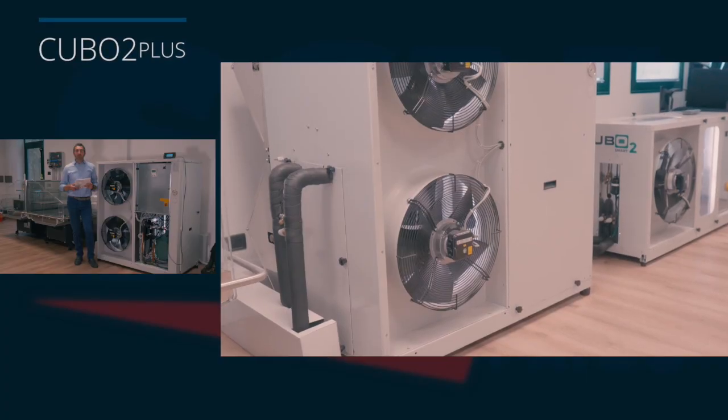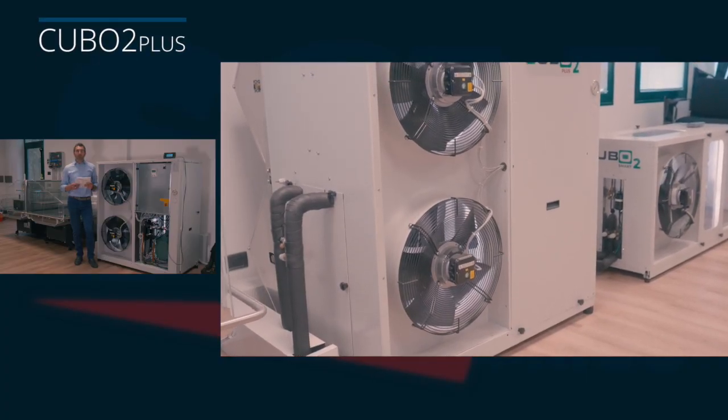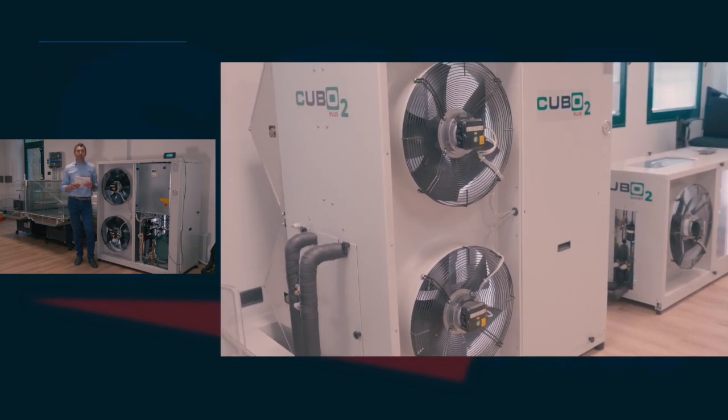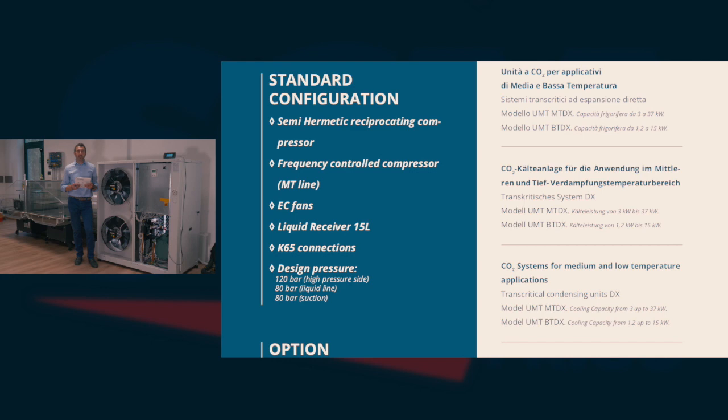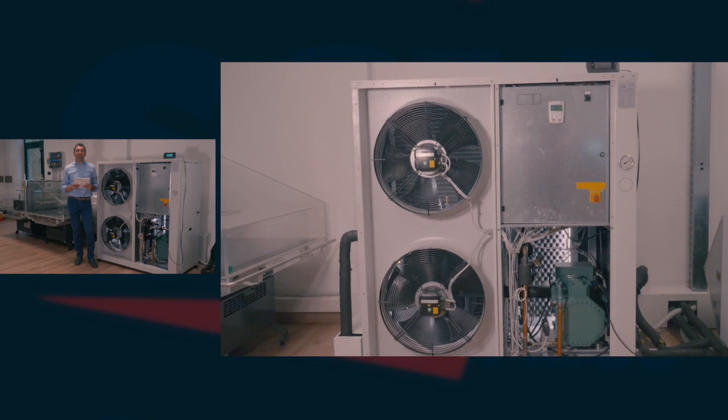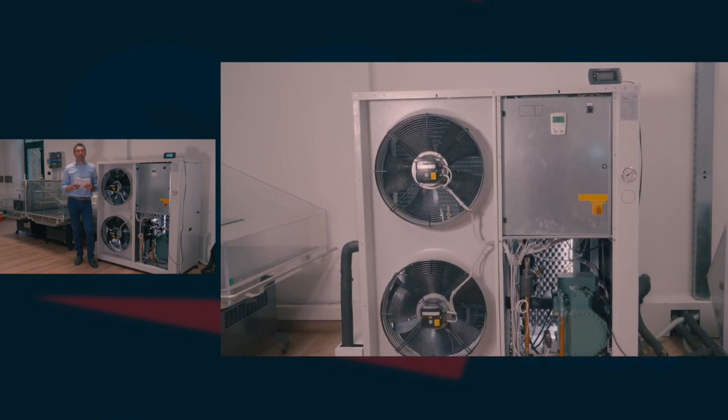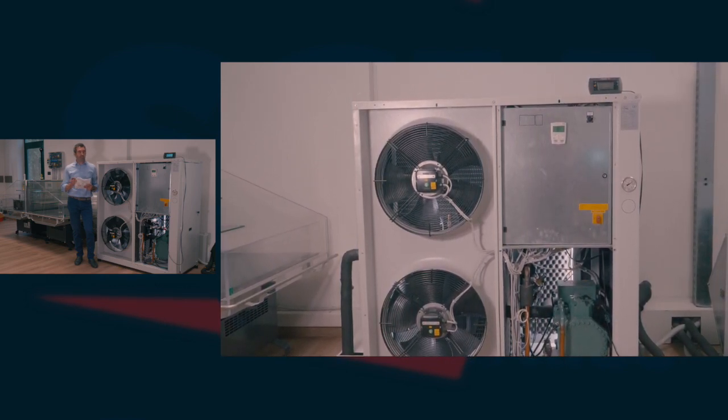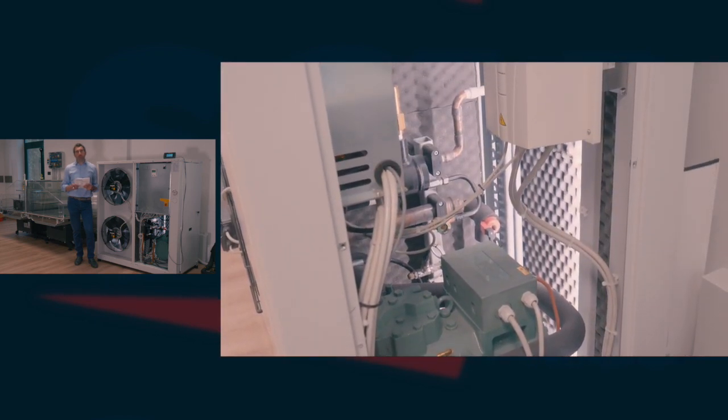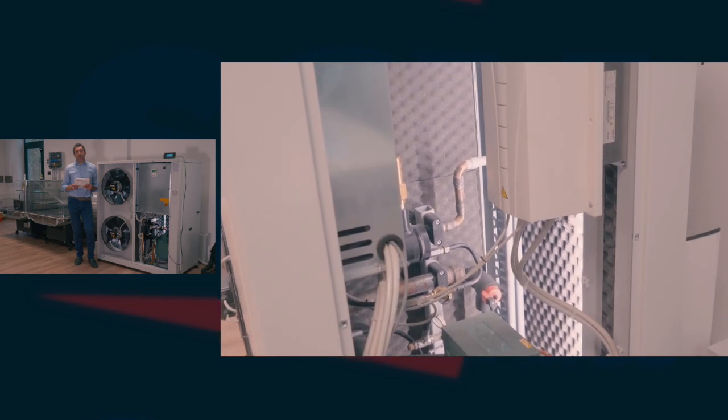This is a medium temperature condensing unit CUBO2 Plus. This condensing unit supplies 9 kW at an evaporation temperature of minus 8 degrees Celsius, and a room temperature of 35 degrees Celsius. This unit is connected to a medium temperature evaporator located in the medium temperature control room, which is managed by an MPX Pro control with stepper expansion valve.